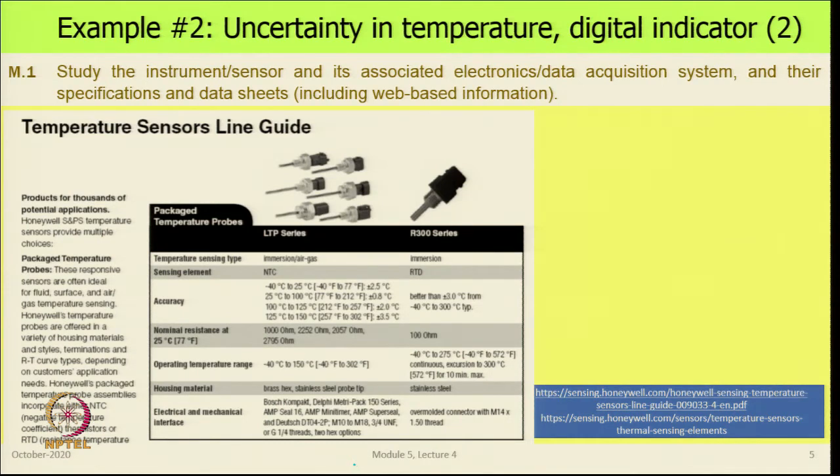All these are from particular manufacturers. There is no real preference. I am using these for illustration only. So, this is a type of sensor. You can see in these pictures that outside there is a hollow stainless steel tube, closed at one end. Inside this, here we have our sensor, and here there is a packaging which is closed.